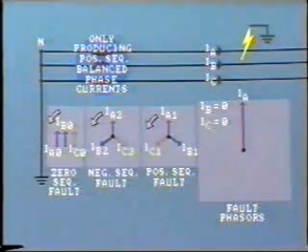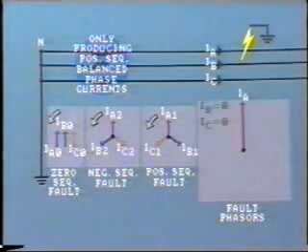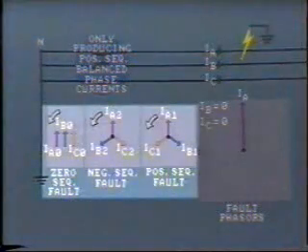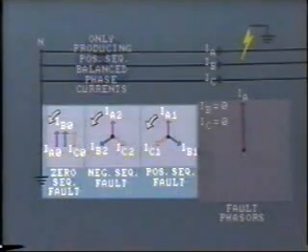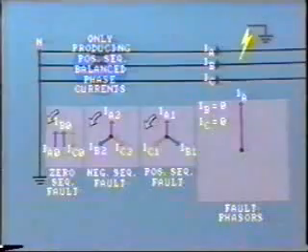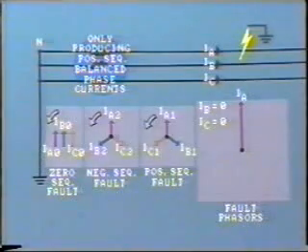This is what we should expect. There is a heavy flow of current in the grounded line, but there is zero current flowing in the uninvolved phases — remember that we are assuming load to be zero. Again, we have seen that the sum of the positive, negative, and zero-sequence components for each phase add up to give us the actual fault values. So we now come to another very important conclusion: where a ground fault exists, all three sets of symmetrical components are present — positive-sequence, negative-sequence, and zero-sequence components. And do note that within each set of components, the voltages and currents are of equal magnitude. The presence of these components provides a useful tool for detecting unbalanced conditions and ground faults.